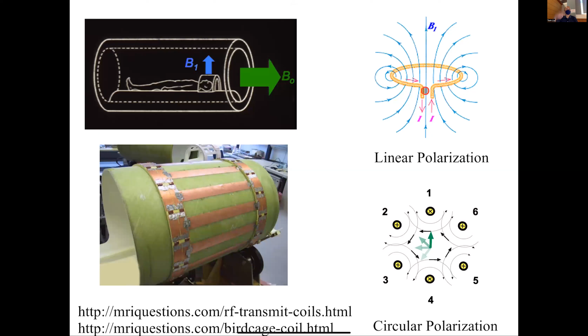So as we talked about before, you could have an RF coil. In this case, it's just being called the transmit coil. All major whole body systems have what's called a body coil. This is a coil that's big and goes around the whole body, and it can both transmit and receive. But over the last 20 years, especially, there has been a trend to use one coil for transmit and then use a lot of smaller coils to receive. There are two advantages of that.